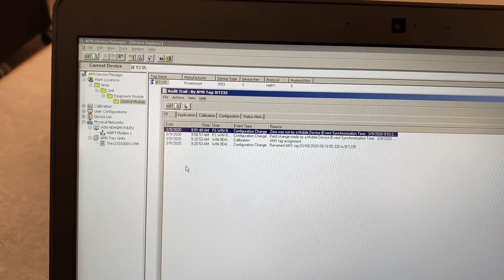All right, so now I want to demonstrate how AMS can track replacement devices. So we've got a second transmitter over here in the back. We're going to be wiring it in, and we're going to be using it as a replacement for our existing transmitter. So something could have happened to this transmitter, could have malfunctioned, we need to replace it. So we're going to show how AMS can document that replacement as well. So the first thing that we're going to need to do is find our device that we're replacing, right click on it and go down to replace.